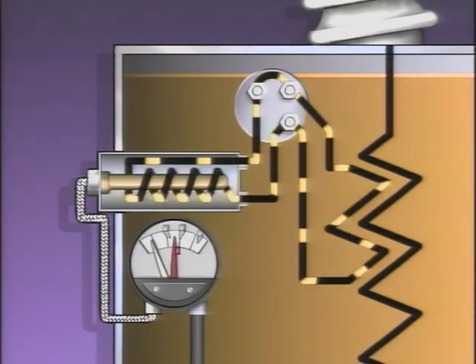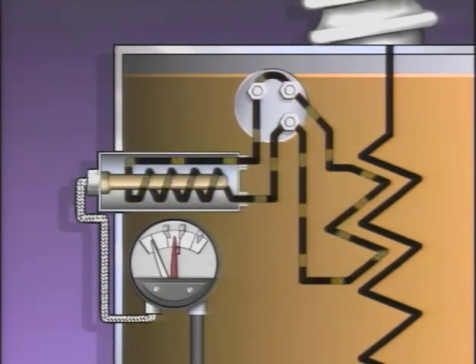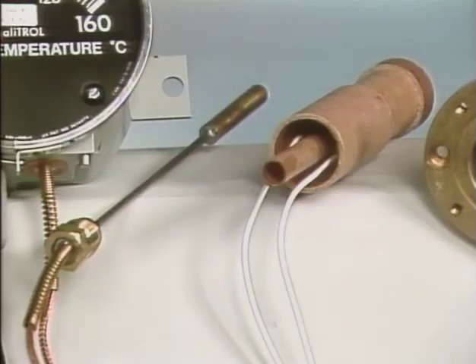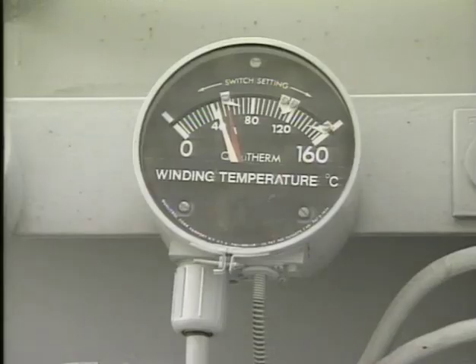The function of the current transformer and the heating element is to simulate the temperature rise created by the power transformer winding. The winding temperature is determined by the load on the winding, the thermal characteristics of the winding, and the temperature of the transformer oil. The heat created by the heating element and the heat of the transformer oil both act on the temperature-sensitive bulb, and the temperature measured represents the simulated winding temperature.